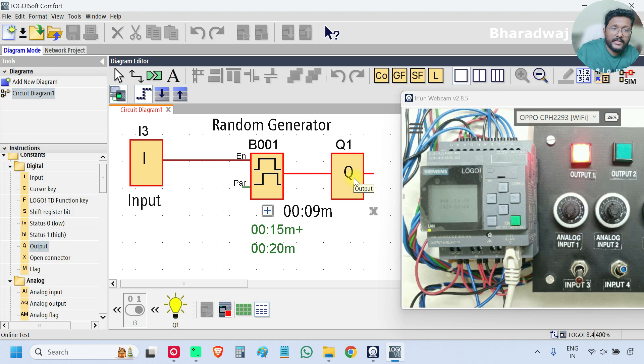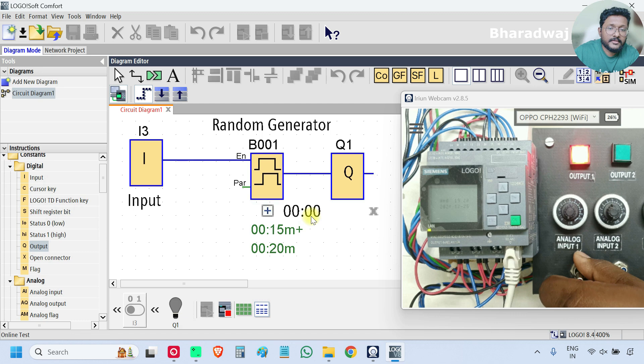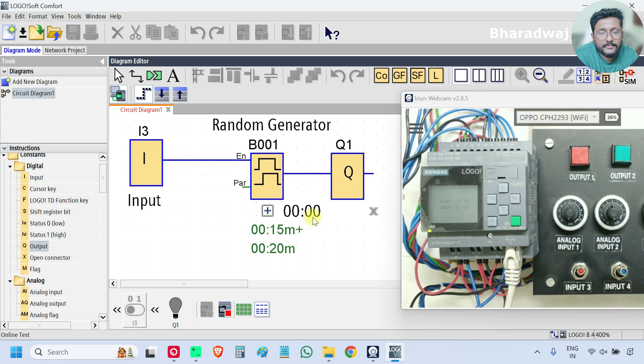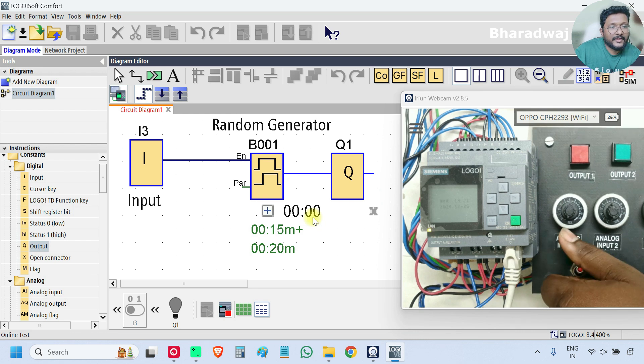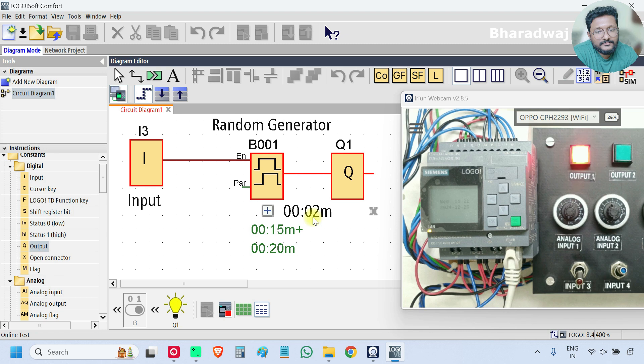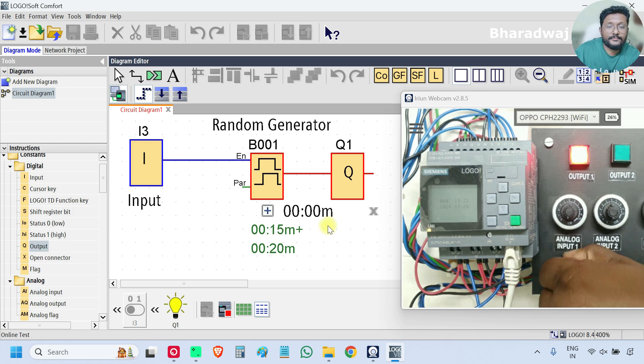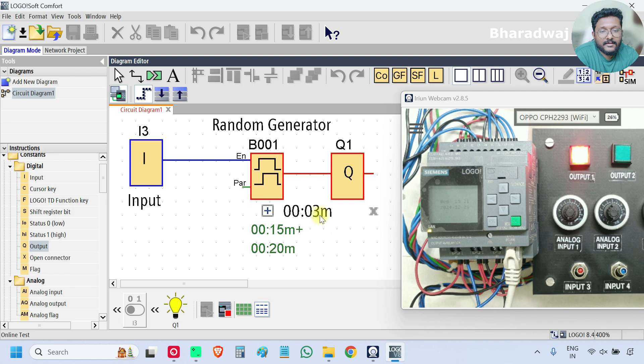Now I will turn off the input — again a new timer will start. It went to zero immediately, meaning it picked either zero or a very small value. So it is difficult to observe in one attempt; we will test again. This time it took two seconds for on-time. Now I will turn it off — see, the value is more this time. We can observe 12, 13, 14, 15, 16 — the off-delay picked 16 seconds.